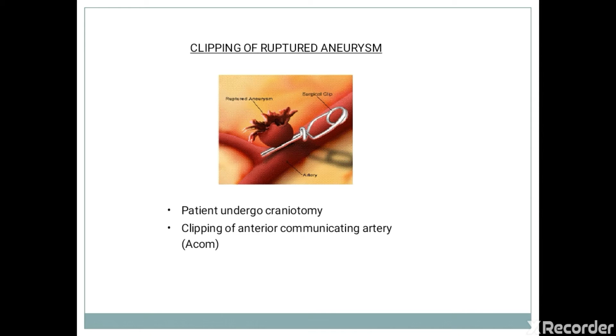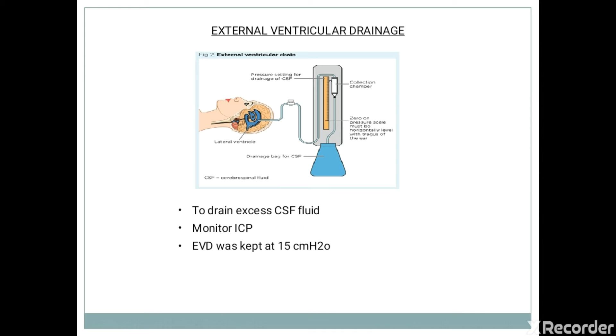Hydrocephalus is a common condition after having SAH. An external ventricular drain was inserted prior to hydrocephalus management. EVD was inserted to drain the excess CSF and to provide ICP monitoring. After the insertion, the EVD was kept at 15 cm water above the tragus to maintain the transducer at the same horizontal level as the ventricle. Improper positioning of the pressure transducer may lead to false interpretation of ICP. EVD drainage is charted hourly.